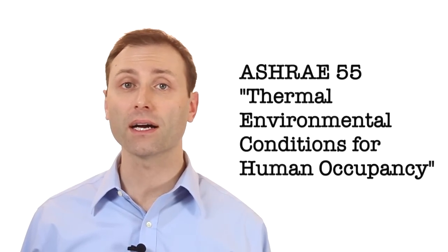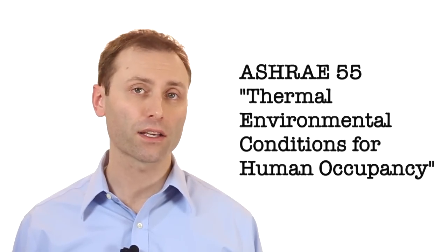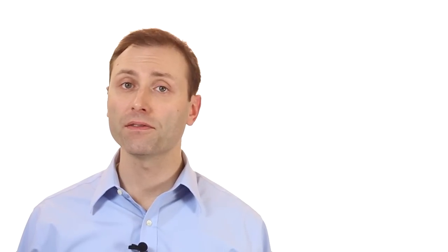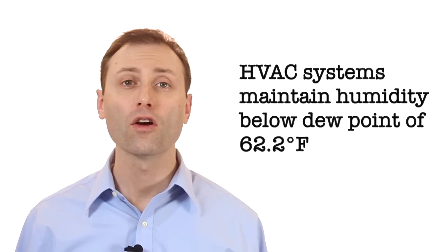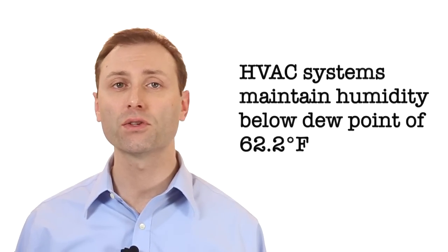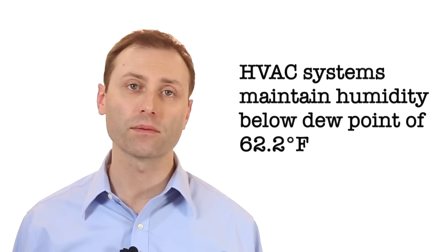Another ANSI approved standard is ASHRAE Standard 55, titled Thermal Environmental Conditions for Human Occupancy. Standard 55 requires that HVAC systems be able to maintain the humidity below a dew point of 62.2 degrees Fahrenheit when using a specific method described in the standard.